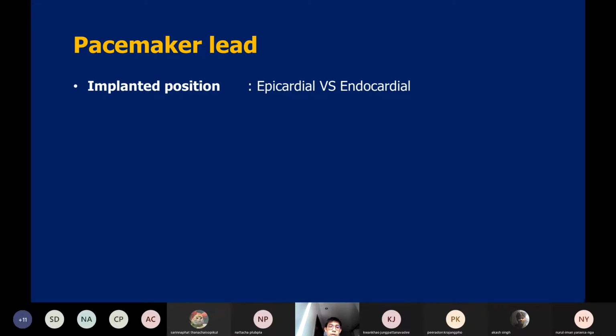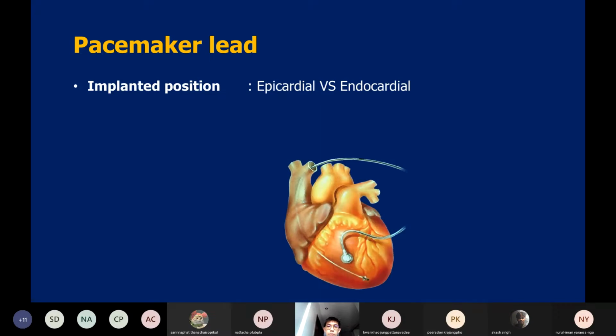And I would like to talk about the pacemaker leads. We can implant the pacemaker leads into two positions. The first one is the epicardium. The epicardium is outside the venous system, in the outer part of the heart. The second one is the endocardium, which is inside the chamber. We put the lead through the venous system into the chamber of the RV or RA. This is endocardial. But for epicardial, you have to operate on the patient and put the lead on the outer surface of the heart.